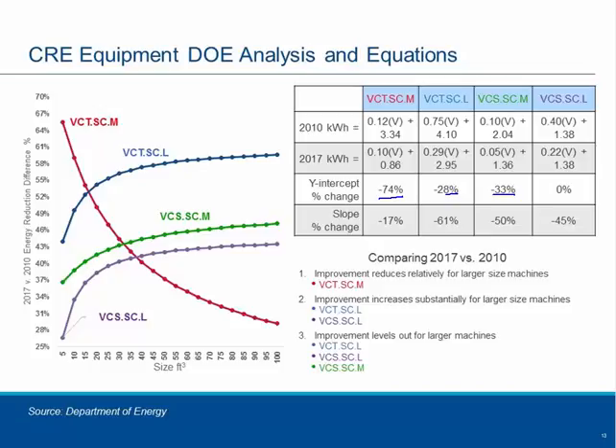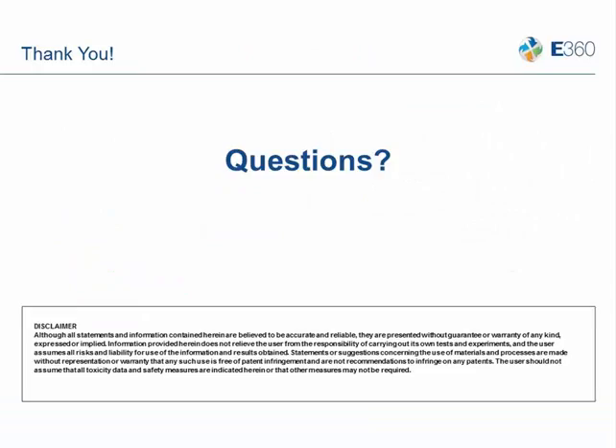Okay. Is Emerson looking into making condensing units for R450 or R513A that have BTU capacity greater than 8,000 BTUs and still be able to keep footprint similar to current R404A models? Yes, sir. For the last 2 years, we've been working as an organization in order to be compliant for not only DOE regulations but for EPA requirements. The answer to your question is yes. The entire condensing unit portfolio that Emerson Climate Technologies offers will be offered as new systems and new condensing units starting in January of 2017 that will in fact be not only rated for 450, 513 for those capacities, but also for 448A and 449A as well as propane. We're kind of in the all of the above options in order providing our equipment manufacturers what they need.